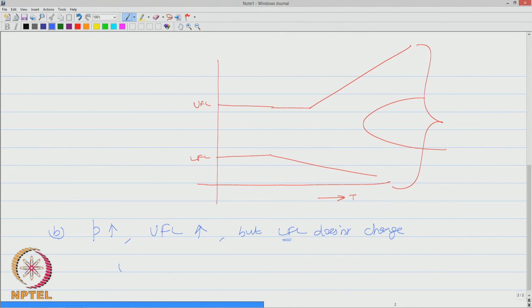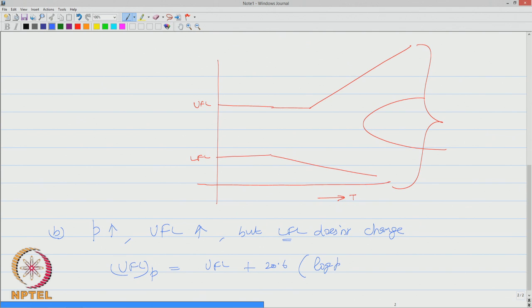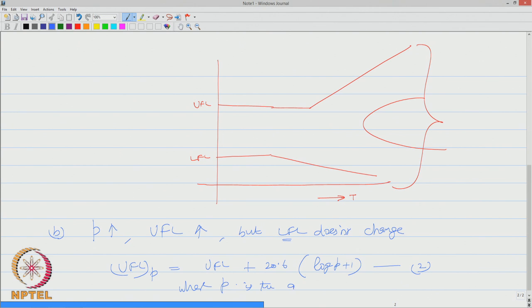So, upper flammable limit at any pressure P can be given by upper flammable limit of the mixture at atmospheric pressure plus 20.6 log P plus 1. That is the second equation we have, where P is the absolute pressure in mega Pascal.